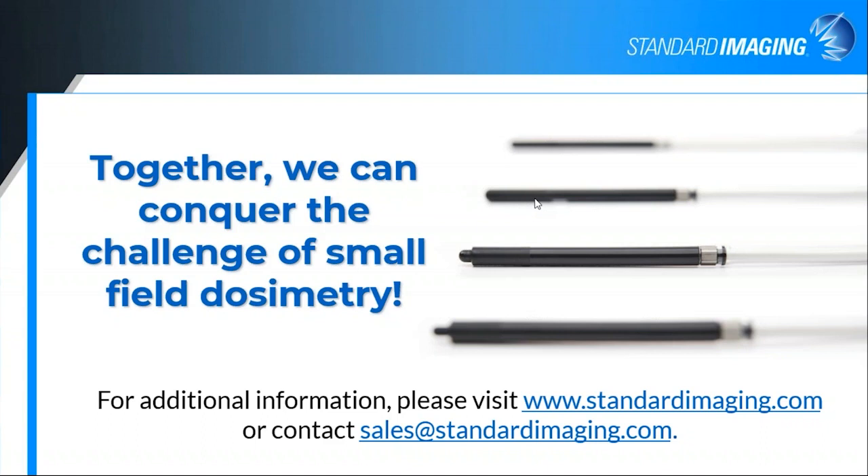Can I comment on film dosimetry in small field? Film dosimetry is good but it's kind of a pain. If you're measuring a larger field, the film dosimetry is quite accurate in terms of profile shapes. You do still need to characterize the response of the film to the radiation so you can convert to dose. The main limitation to keep an eye on with smaller fields is that depending on your scanner, there can be some light scatter from a very small dot that decreases the signal or increases the amount of light reaching your scanner from scatter within the scanner itself. This can artificially flatten or smear out your measured profile on an extremely small field. For the most part you'll be fine above maybe 5 or 6 millimeters, but below that you would really need to be careful.